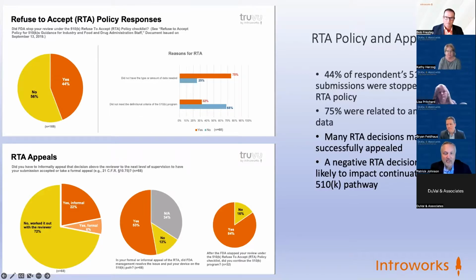Yeah, I would agree, Lisa. I think, again, the primary issues we're seeing with RTA are when there is a failure to have complete content in the submissions themselves. At least in our experience, we're usually avoiding that upfront with the ones that we're working on directly prior to submission, and potentially including that RTA checklist in the submission to really identify where those elements are covered. So it's harder for FDA to argue back that the 510K elements are not included.